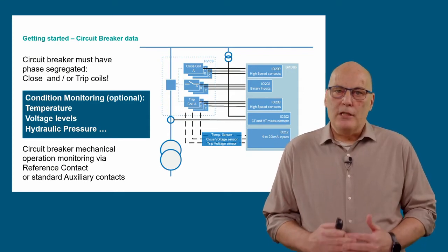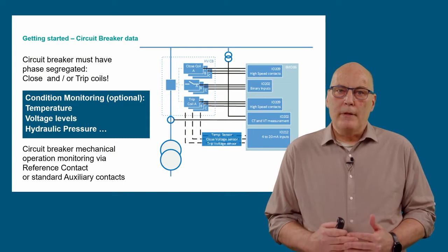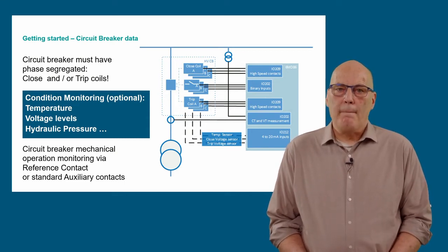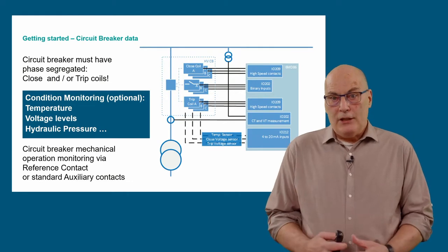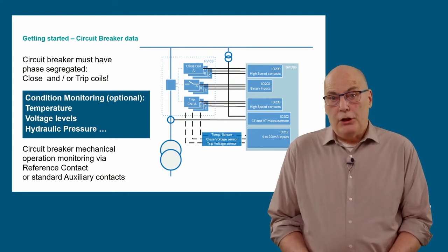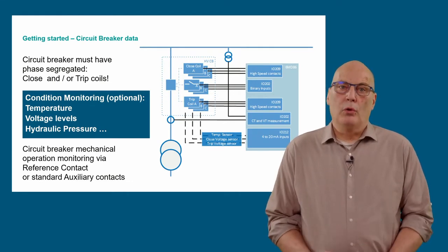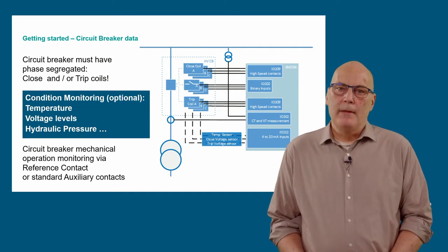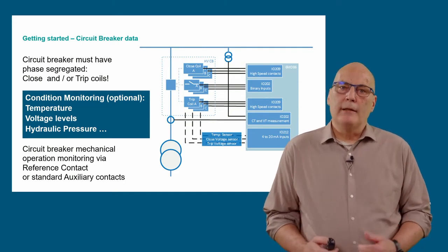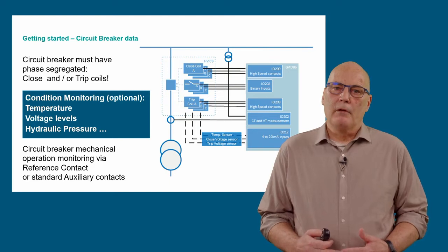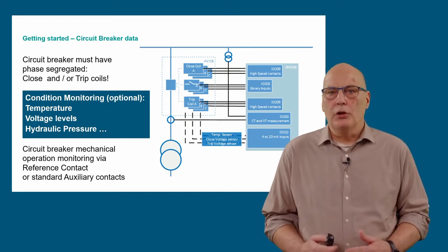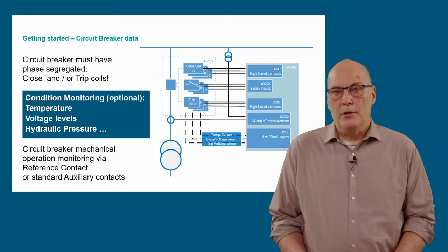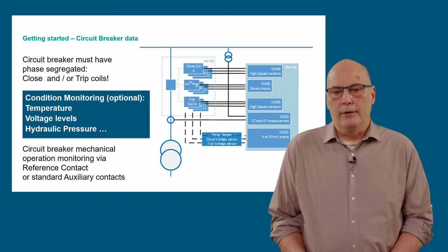This phase-selective connection of the closing and/or trip contacts is a must for the point-on-wave application. The mechanical circuit breaker position during switching can be obtained with standard auxiliary contacts via binary inputs. If the breaker has a reference contact with more accurate switching position status, this can also be implemented via transducer input on the IO 212 module. If conditions such as ambient temperature, hydraulic pressure, or control voltage have an impact on response time, this may be compensated in the point-on-wave function via transducer inputs.